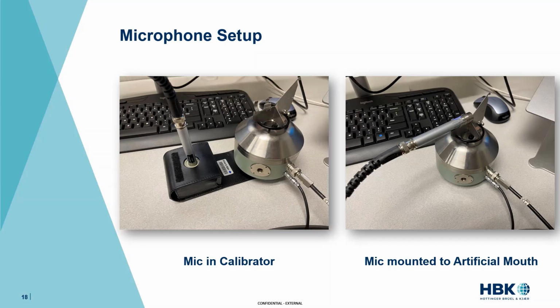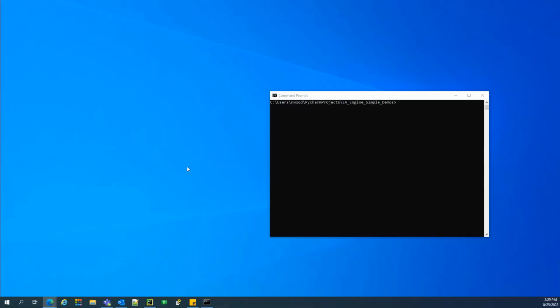It's a playback device that's designed to mimic human voice field and adheres to all those technical standards on speech playback. So we'll go through what the process of it is to set up calibrated equalized speech out of the 4227. So firstly is setup and calibration.